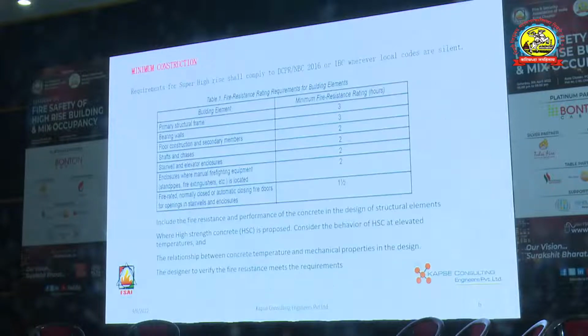Redundant power, which we just spoke about. Interior flame spread finishes and ability. So in NBC it's written class 1, but it's not defined what is class 1. So I believe you can follow an international code for that. Circuit integrity cable, my friend just now talked about circuit integrity. IS 17505 is the latest code that has come about circuit integrity, and they have defined where to use what type of cables. So you need to pick up those particular aspects of circuit integrity.